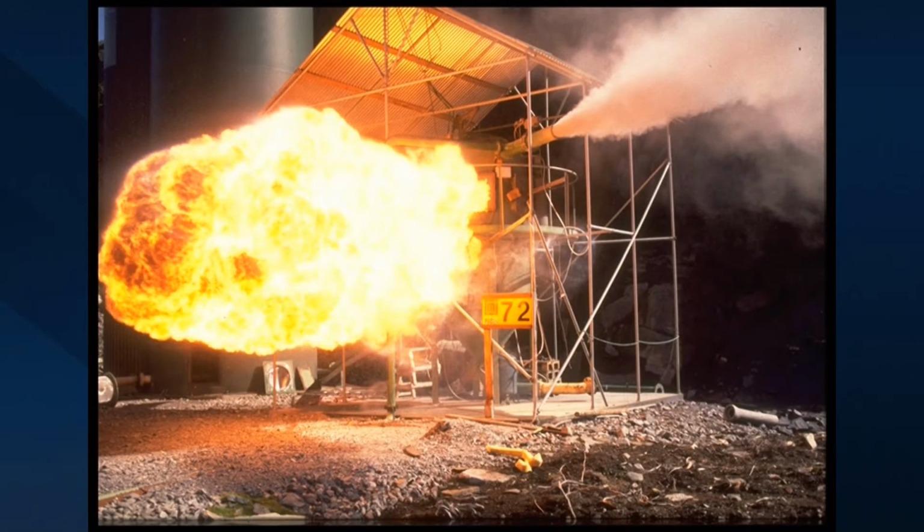Okay, and then here you have again baghouse explosions. What we learned from that is, if you have an explosion in a baghouse, stop the flow of air as quickly as possible. Otherwise you burn everything down, because there's enough fuel and you really melt everything.